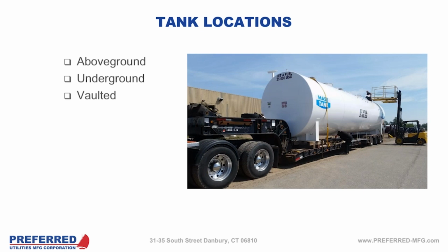As far as construction down where you are, Brent, when you're looking at an above ground or a vaulted tank, when I say vaulted, I mean not direct buried. It's either in a basement in the building envelope, or in its own separate concrete vault outside. Other than the vapor monitoring, is the construction of the tank fairly similar? Because we would do almost exactly the same type of construction for above ground as we would vaulted. Exactly the same, really. All they do is have a concrete vault around it that you can usually enter in some way, whether it's opening up doors or so. In basements, for instance, if the building is just being built, you will find tanks in basements just to conserve space. They put them in the lowest area of the building. But those are just above ground tanks that are surrounded by concrete, more or less.